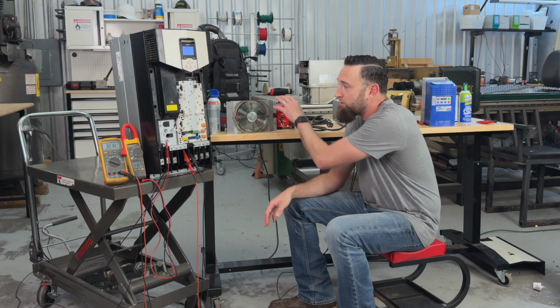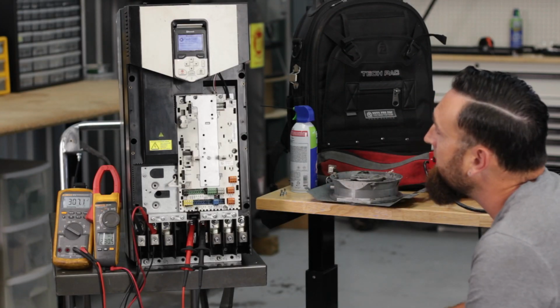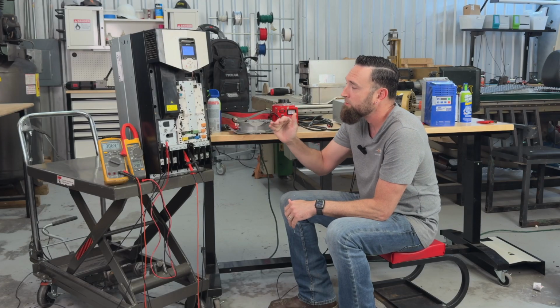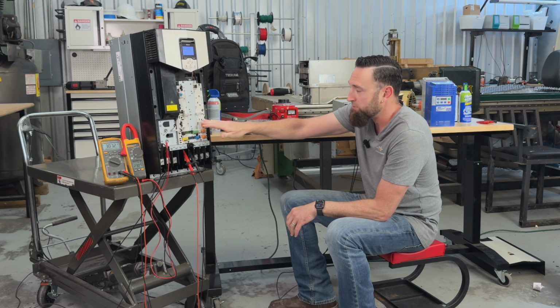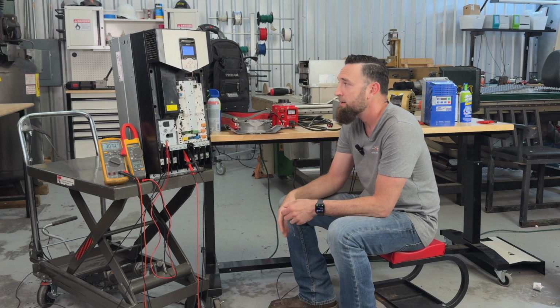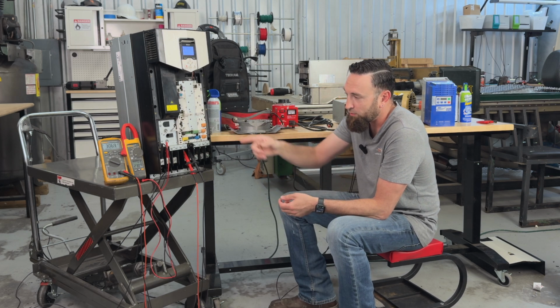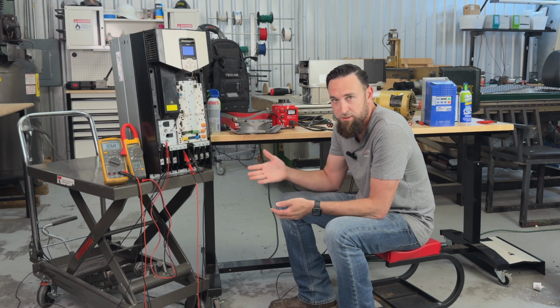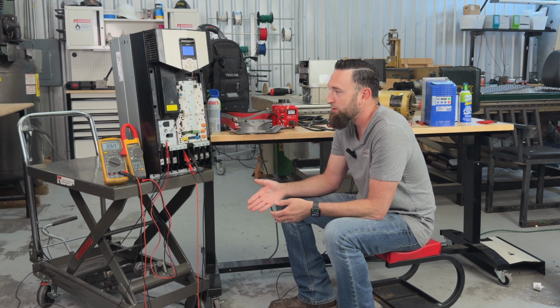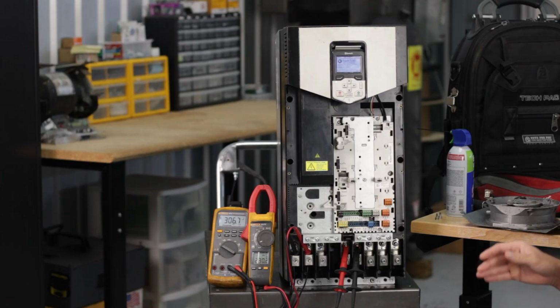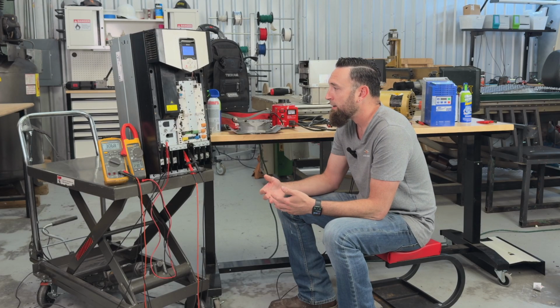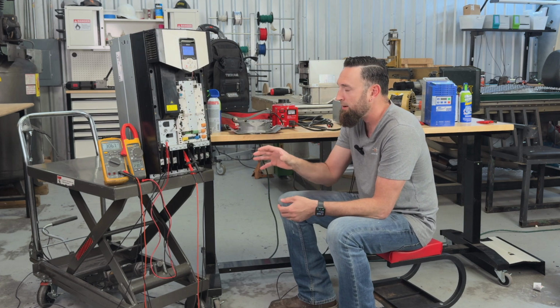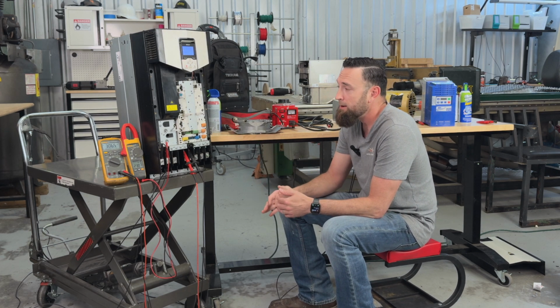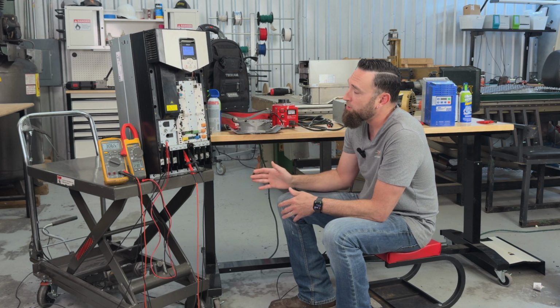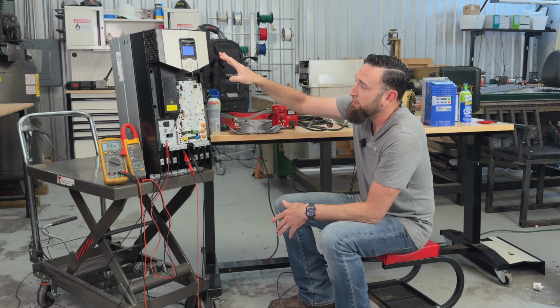We ended up taking out the DC cooling fan. This is a 24-volt powered unit, and when the DC bus reached about 90 volts, the 24-volt DC power supply, which powers the control board, keypad, and cooling fans, would kick on, and there was a fairly significant voltage drop happening because of the pre-charge resistor in the circuit. This stays in the circuit until the bus reaches a certain level and the SCRs are gated on fully, bypassing that resistor. So for now it was on, and we were seeing a significant drop. For that third 25-volt increment, we actually did 35 volts to get over that hump. Once it powered all the way up, we got full voltage and everything came online.